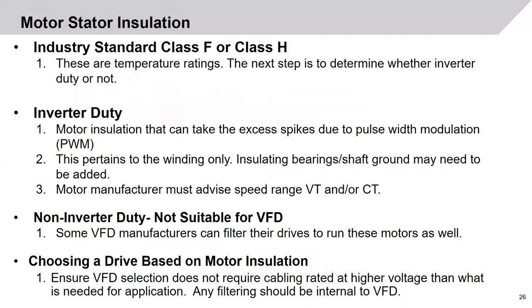Motor stator insulation: class F or class H insulation are temperature ratings and have nothing to do with whether a motor can be on a VFD. The next step is to determine whether the motor is inverter duty. If the motor insulation is considered inverter duty, that means the motor insulation can take the excess voltage spike due to pulse width modulation (PWM). However, inverter duty rating pertains to the winding only — insulated bearings and/or shaft grounding may still need to be added. To be inverter duty, the motor manufacturer must advise the speed range for variable torque (VT) and/or constant torque (CT). There are some non-inverter duty motors not suitable for VFDs; however, modern VFD technologies allow some manufacturers to filter their drives clean enough to run these motors as well.